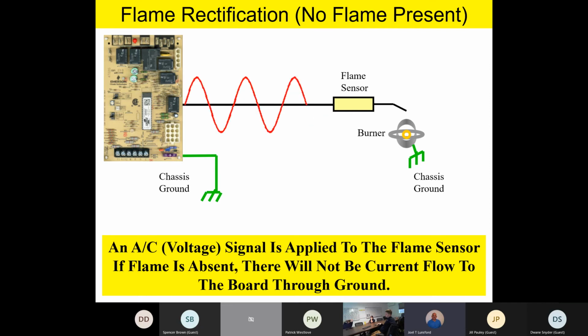Now, it should be noted this is line voltage driven. What I mean by that is, if you've got 120 volts to the control board, there's going to be 120 volts or very close to it on the flame sensor. Now, catch this though. This circuit is an extremely high resistance circuit. We're talking hundreds of millions of ohms resistance. So there's no current to speak of there. In other words, if you touch that flame sensor, it's not going to shock you. If you shorted the flame sensor to the side of the burner, or to ground, it's not going to burn anything up.